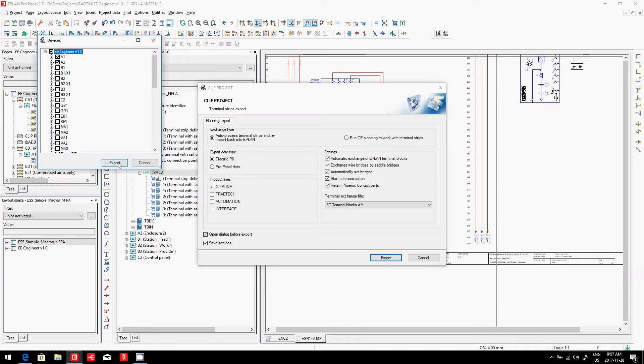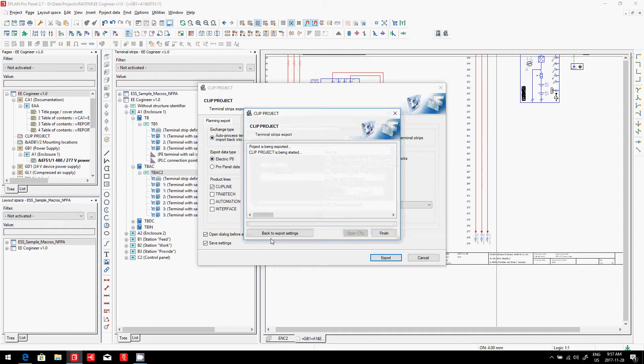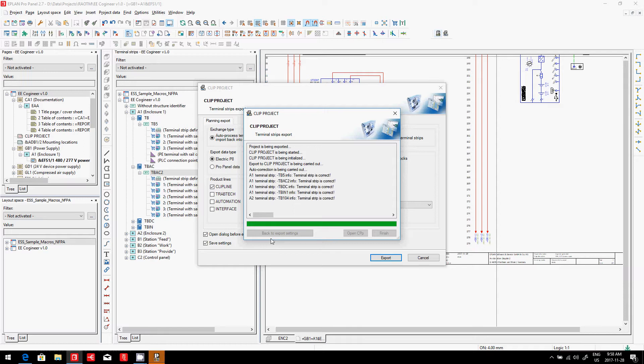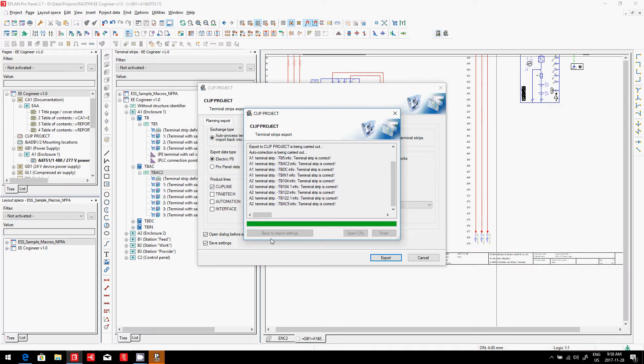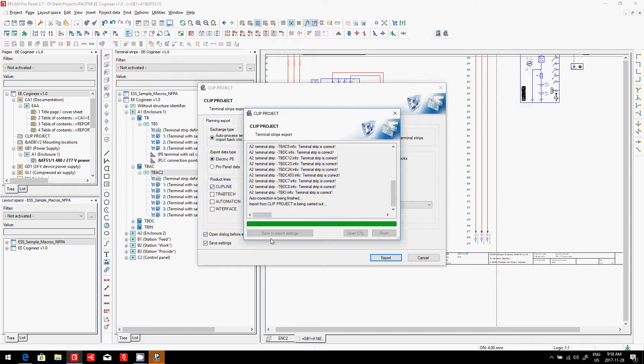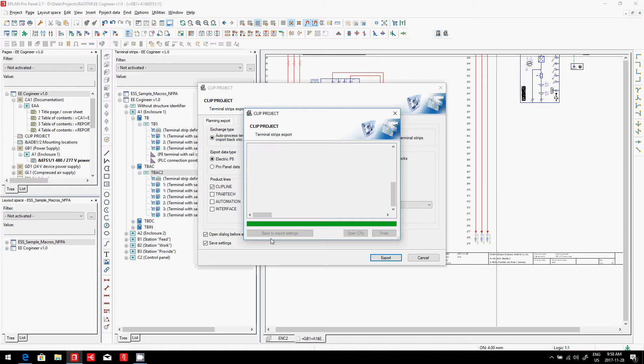It will go through the different terminals, the different terminal strips, and check them for accuracy. It will check which ending plates you have selected—if it's actually the correct one, if it's too big—it's going to change it and give you some error messages in case something works out wrong. It can even pick some terminals based on a selection list that you have.